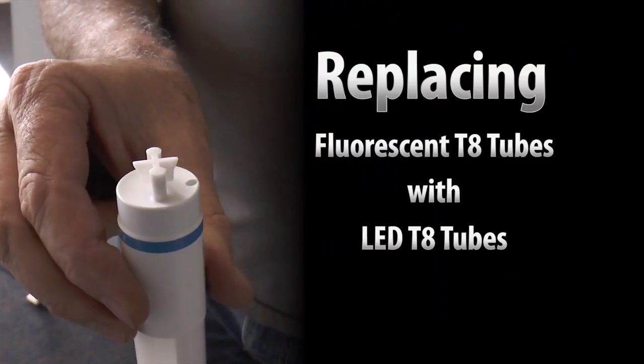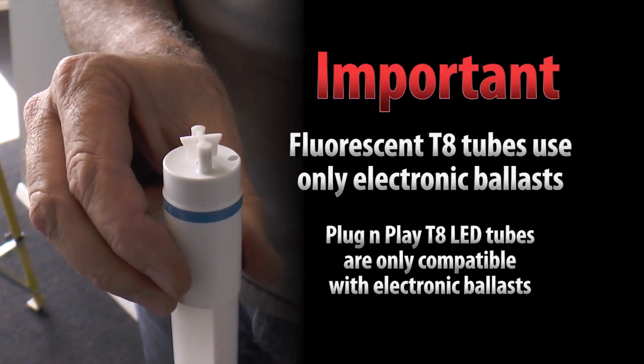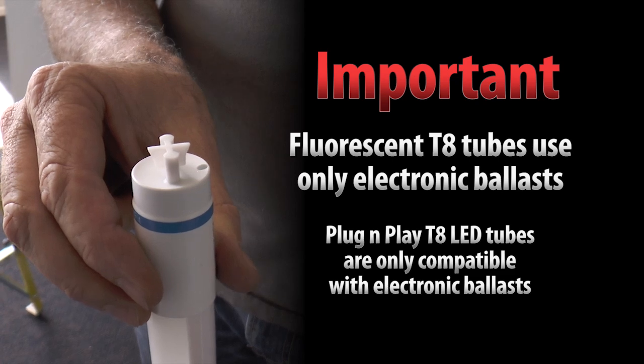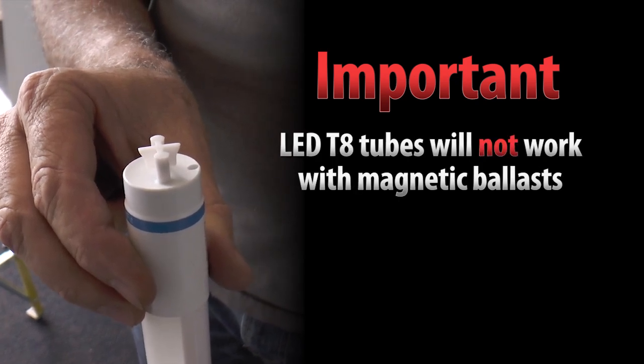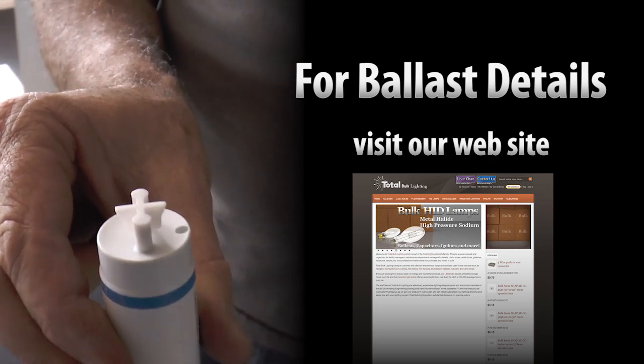Now we're not changing from T12 because the fluorescent T8 fixtures have electronic ballasts in them. This won't work with an old school magnetic T12 ballast. And on our website we list pretty much every electronic ballast that's going to work.